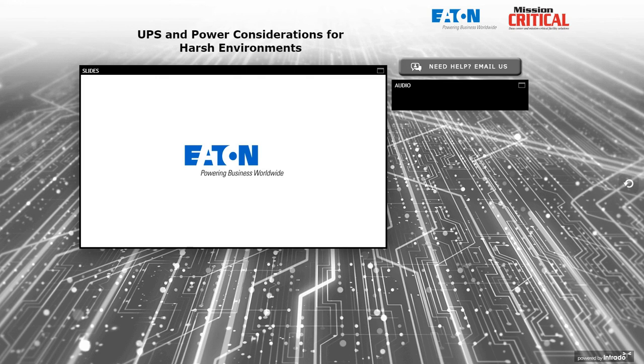That's a good question. Always like these. That's an excellent question. And in the older days, back in the days when I still had hair, we didn't put fuses in the bypass because we didn't want a device in there that could perhaps cause a failure of the critical load if the fuse were to fail unexpectedly or at a lower level than we would intend. However, UL and fire codes and electrical codes got involved quite a few decades ago and said you will have protection in the bypass line.